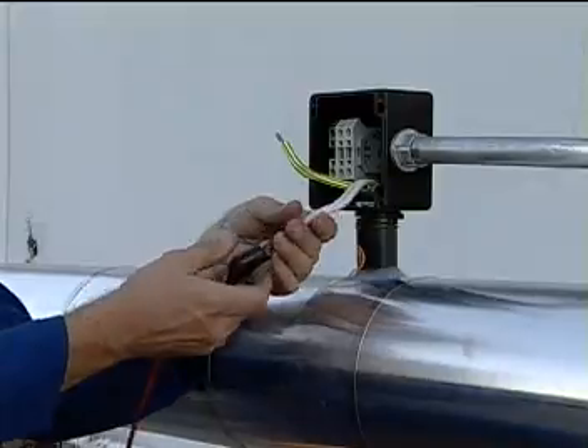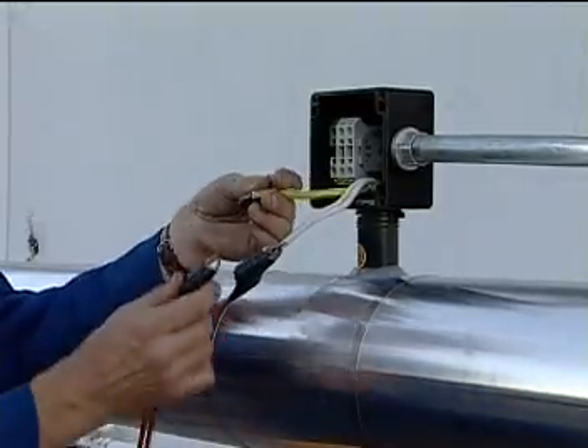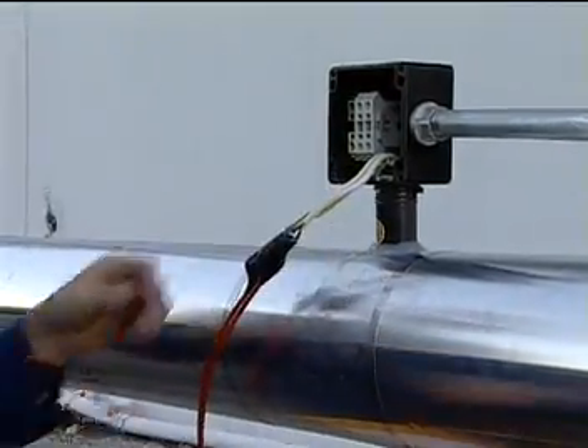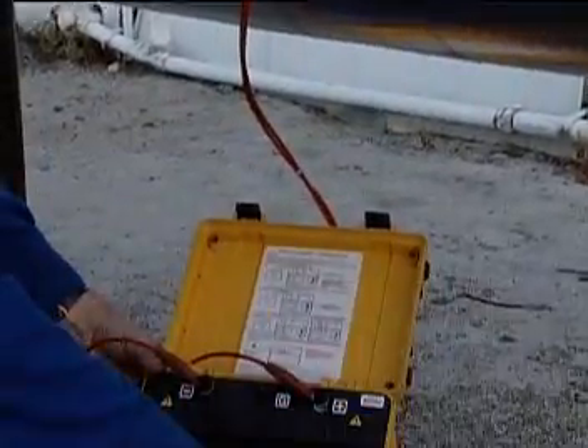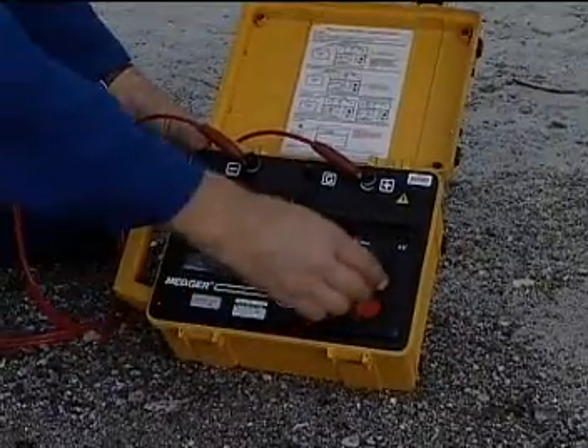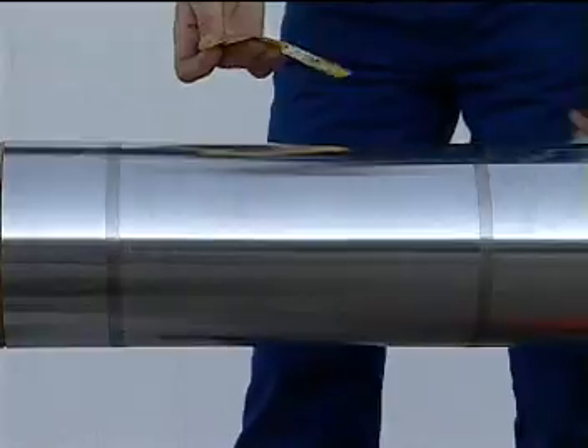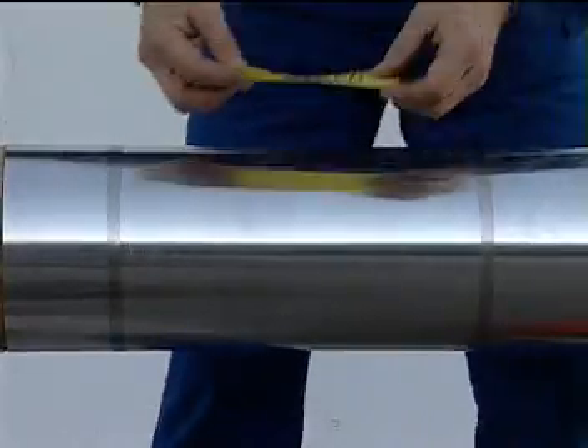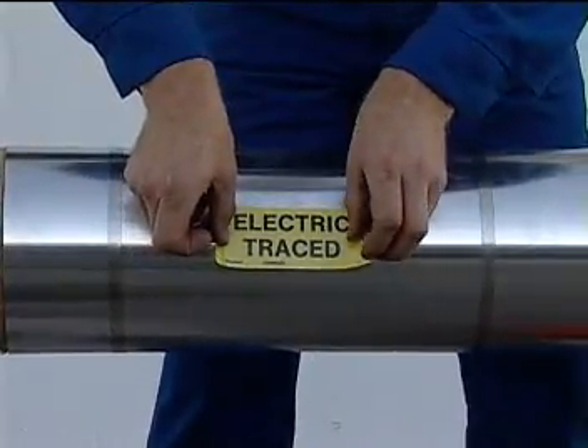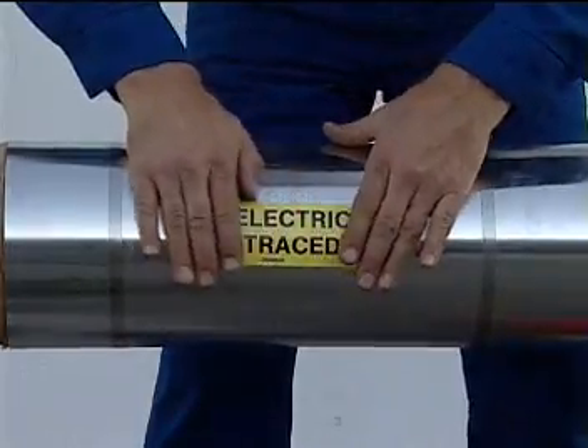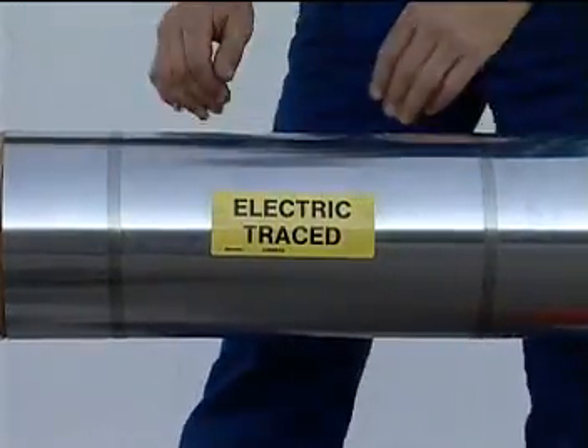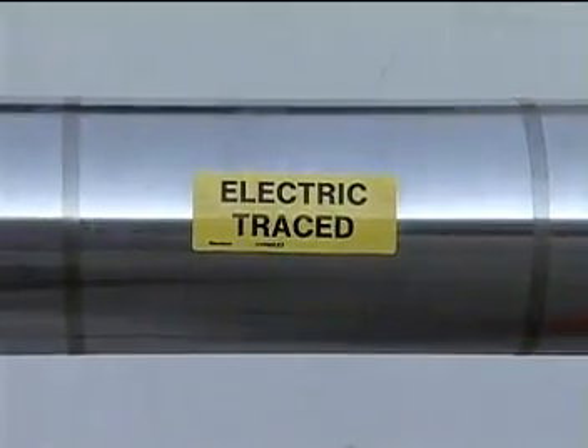Especially be sure that the cable wasn't damaged during the installation of cladding. Confirm that the cable has not been damaged by testing the insulation resistance once again. Once the integrity of the system has been confirmed, apply electric trace labels on the outside of the insulation at 10-foot intervals. These labels should be on alternating sides of the pipe and should be easily visible.